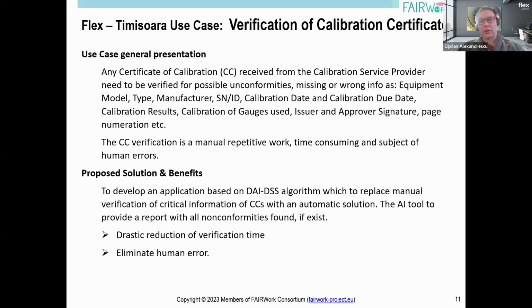The use case in Flex Timișoara was to verify certificates of calibration. As a general presentation, all the certificates of calibration received from the calibration service provider need to be verified for possible nonconformity before being uploaded in our quality system. The nonconformities are missing or wrong information about the equipment model, type, manufacturer, serial number or ID, calibration date, calibration result, issuer and approver signature, page numbering, and so on.